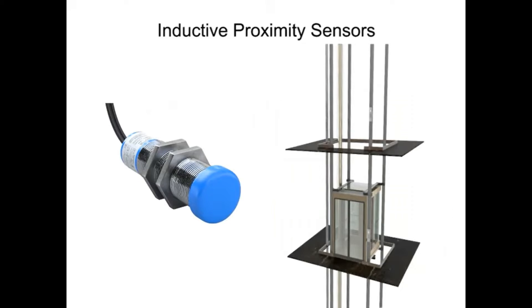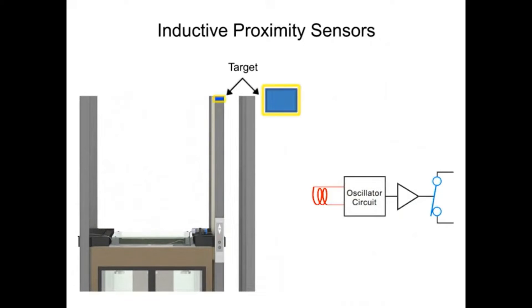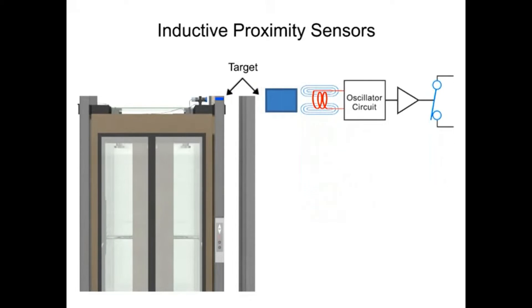Inductive sensors can detect a target from 0.5 mm to 40 mm. They only detect metallic targets and therefore use a magnetic field to detect its presence.